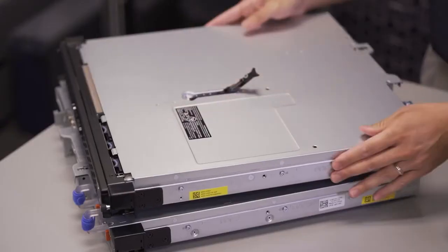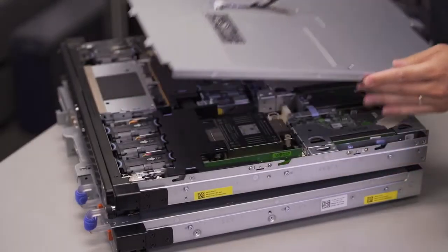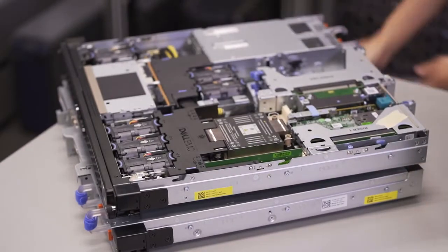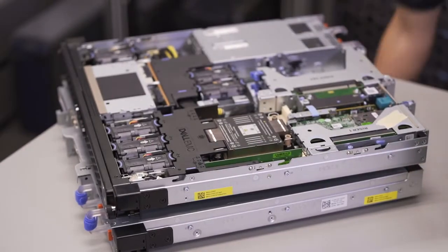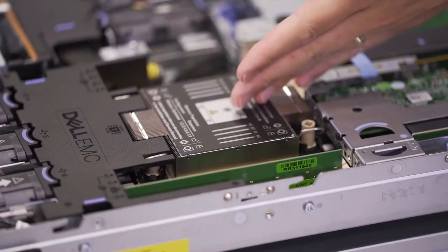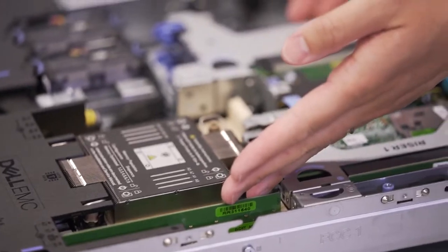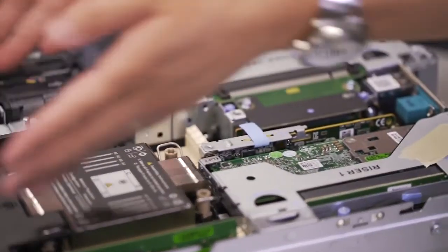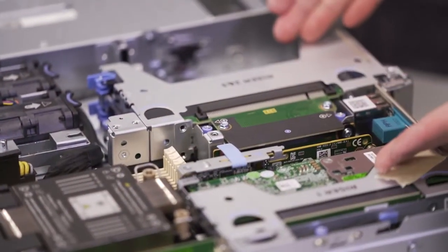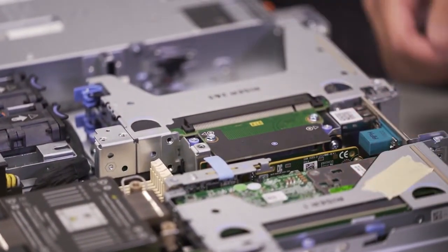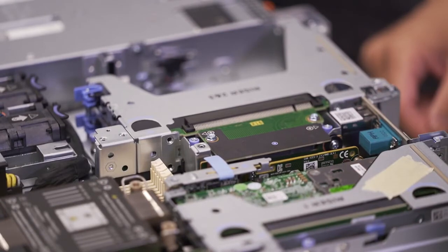And it's this short depth that creates a layout advantage so that most of the critical internal components, like the processor, memory, and PCI cards, receive ambient temperature air, minimizing preheat from other internal components.